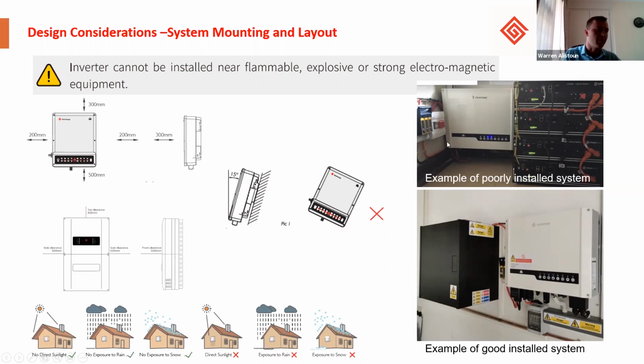So this here will be very difficult should you need to do a Wi-Fi reset and get into the Wi-Fi reset button. Looking at the system below, the inverter's got enough space left to right, top to bottom. All the connections are very accessible, well laid out, and all the warning signs have been labeled. So the restrictions with GoodWe is it's a fanless design, so it uses a heat sink and natural convection. We cannot tilt the inverter in this orientation, but we can tilt the inverter to a maximum of 15 degrees in this orientation. And this sometimes is very useful when doing a server cabinet design, and it can help reduce a little bit of space. Otherwise, normally on a wall, if your wall is not perfectly straight, it's not a problem. You can do up to 15 degrees.